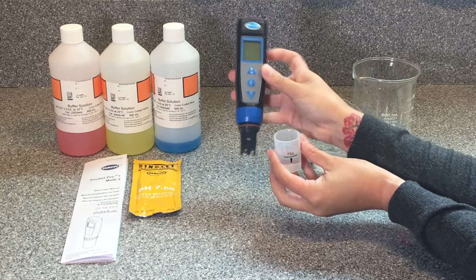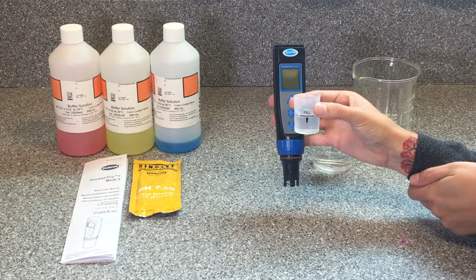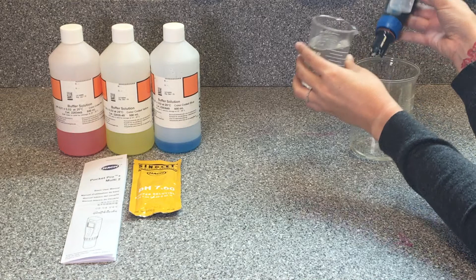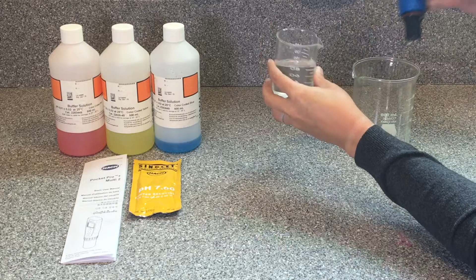Our first step is always going to be to discard and rinse both the sensor tip and the cap. We'll discard the old water and then use our sample, in this container here. If you're in the field, you can do it directly from your water source, otherwise from the container you brought back to your office. Rinse the tip and then fill and empty the cap a couple of times, to make sure all of the old water has been replaced with our sample water.